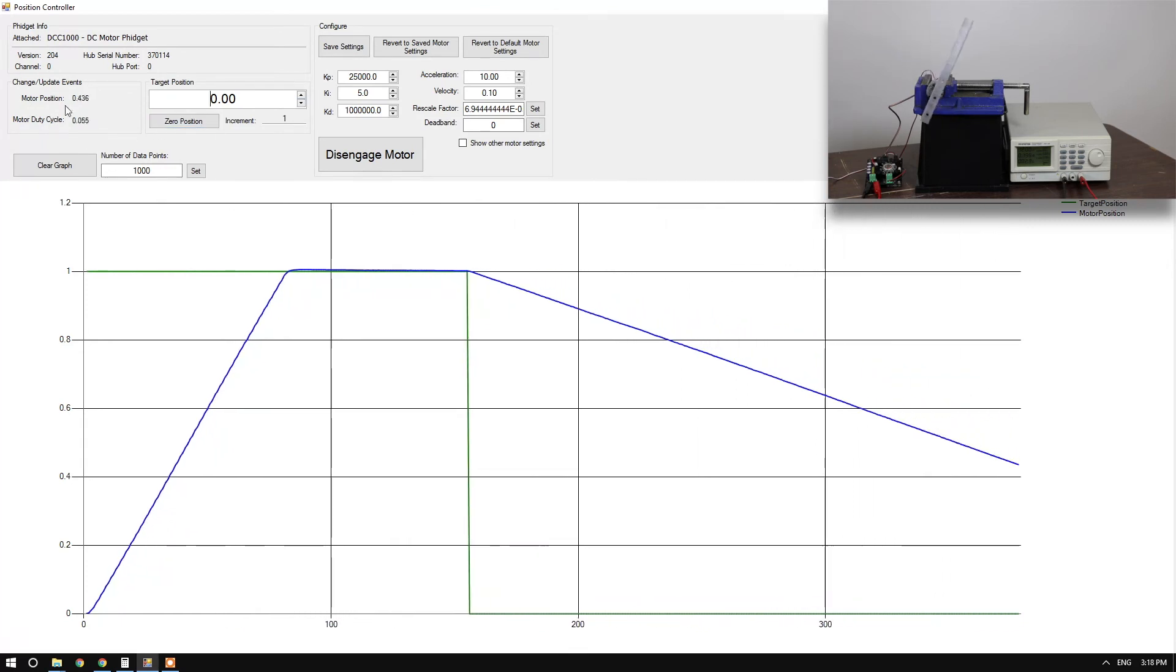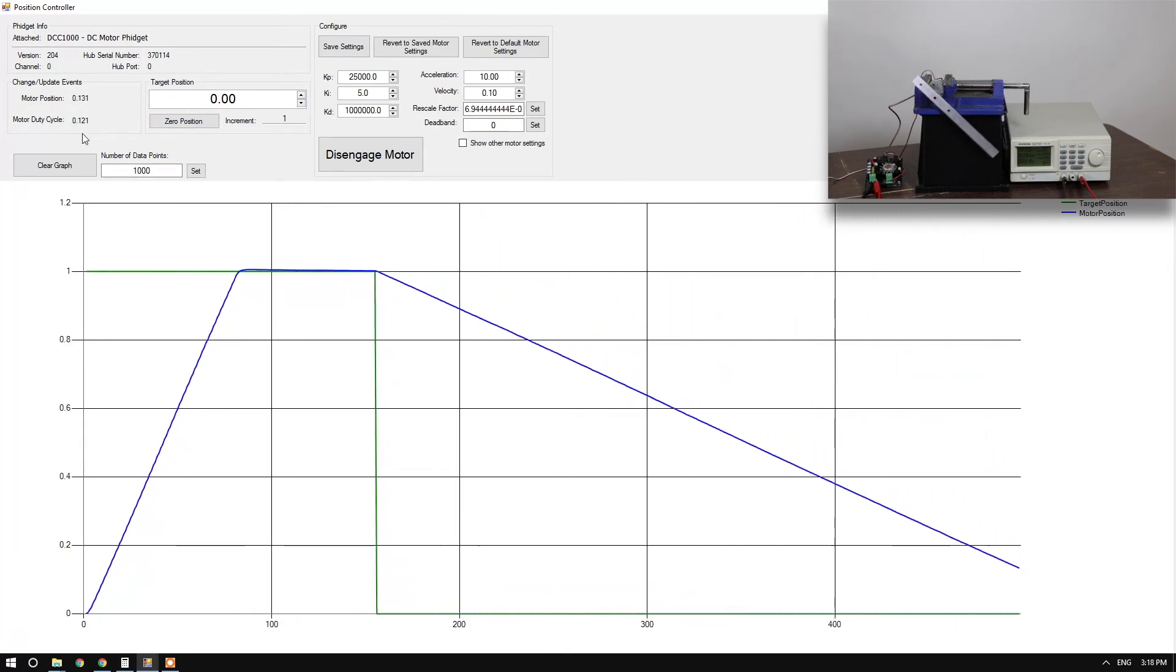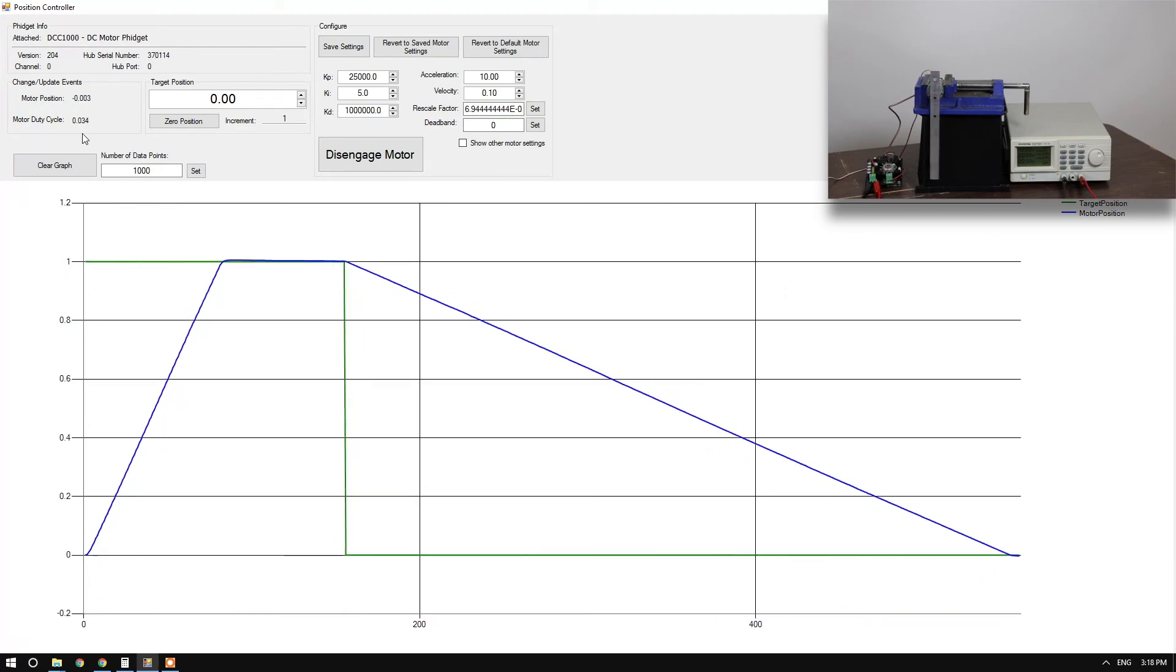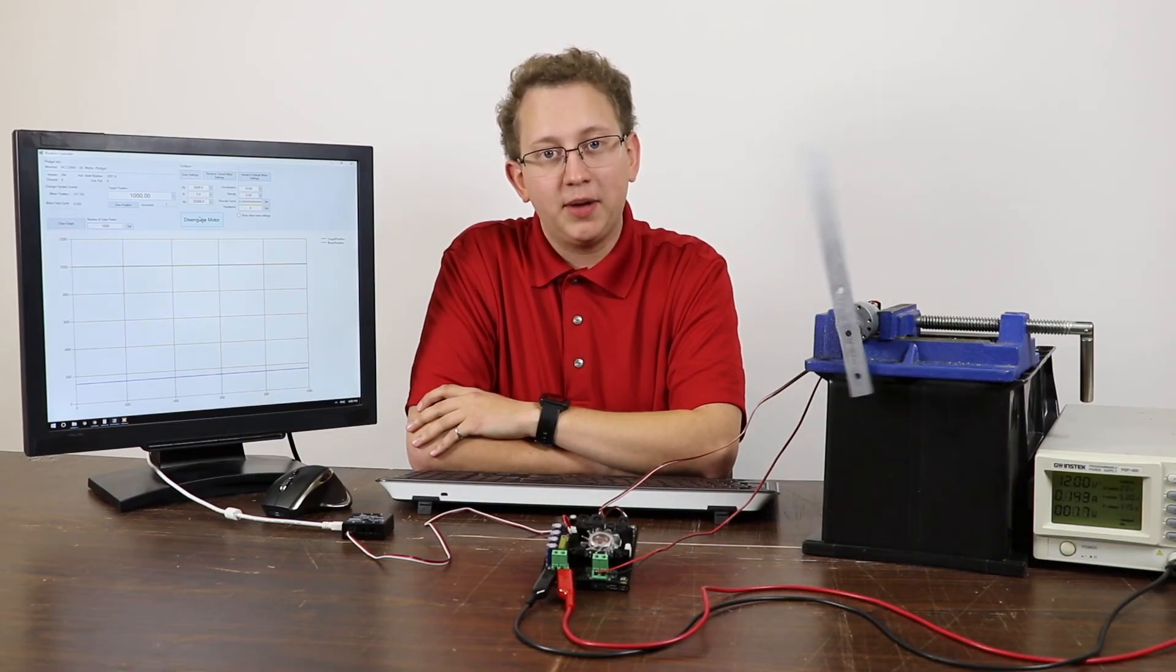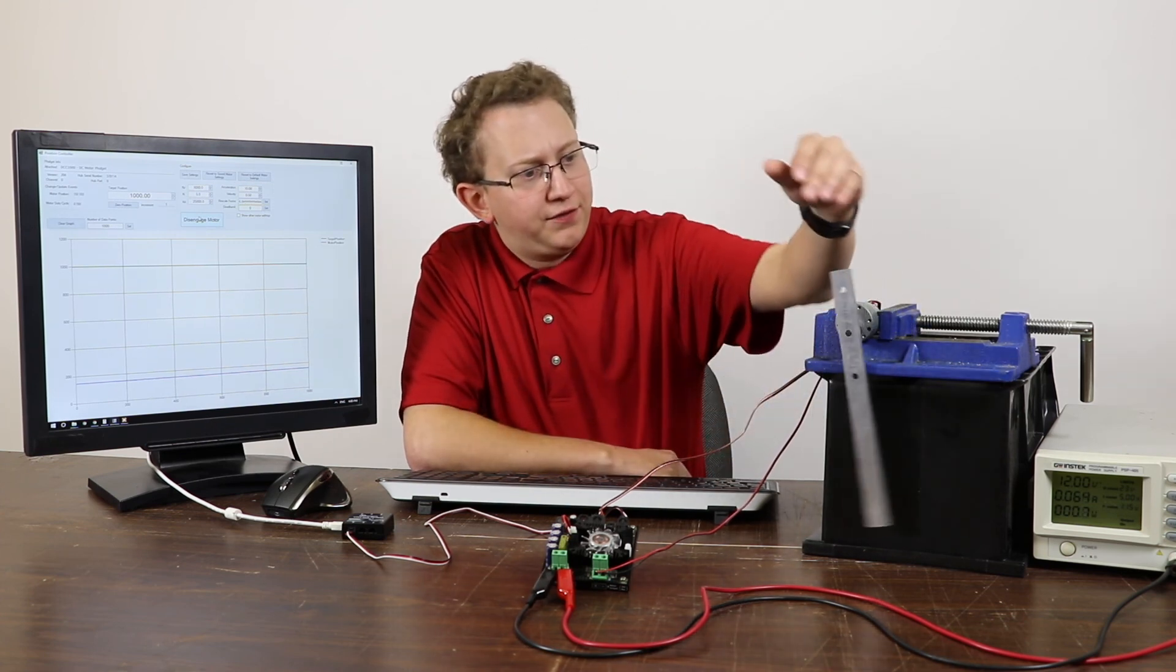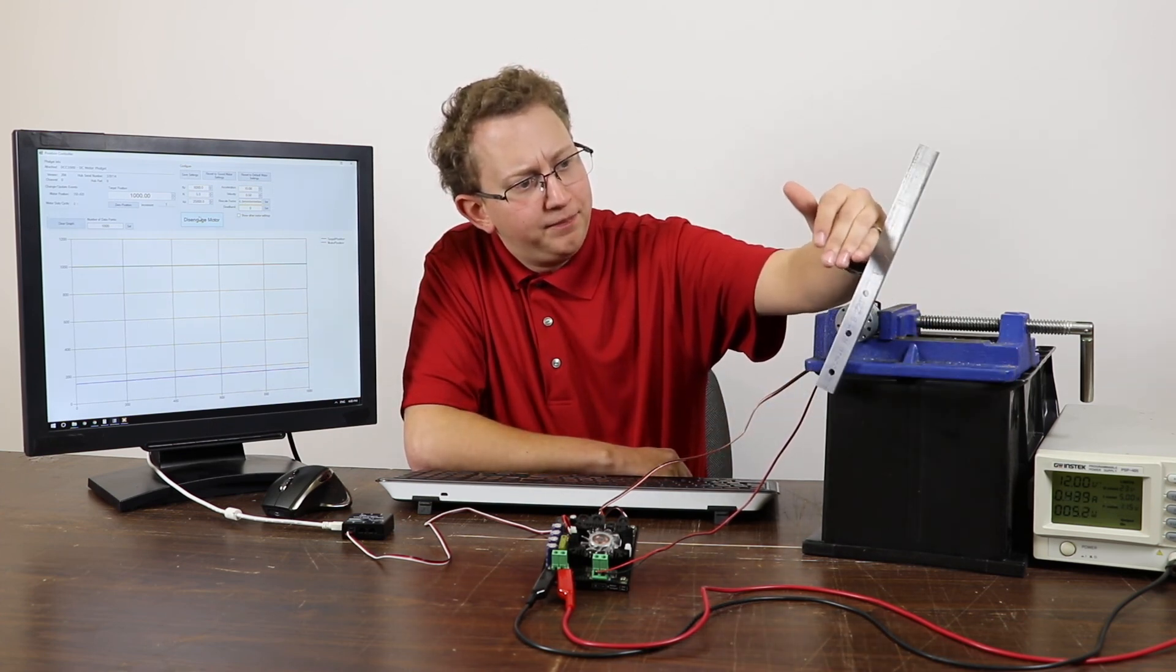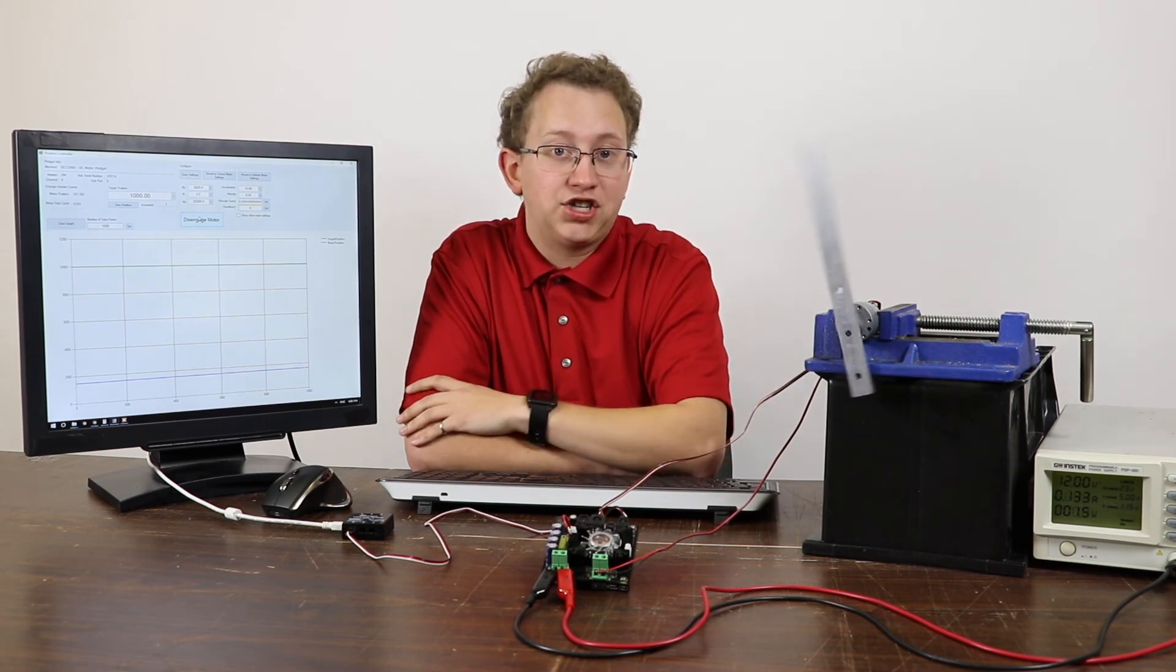If you check the duty cycle, it's interesting to note that the motor fights the other way to maintain speed on the way down. It's important to note that the velocity limit is not a hard limit on the motor's velocity. If it falls behind its generated path, it will exceed its velocity limit in order to catch up.